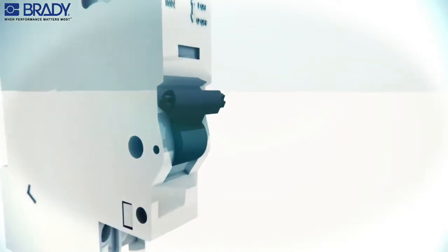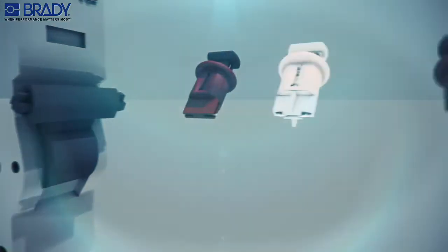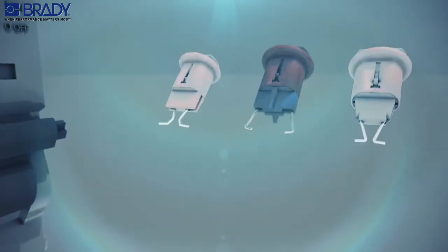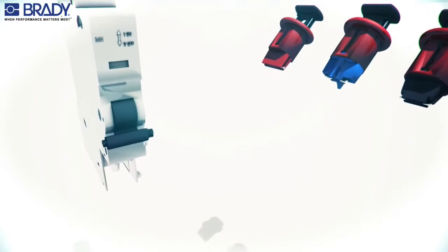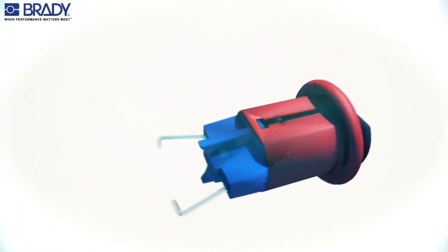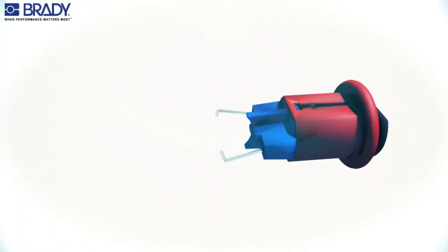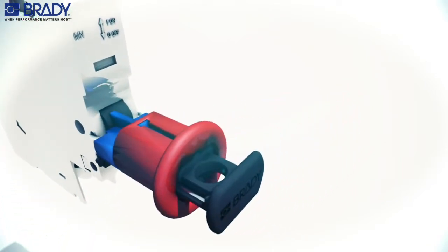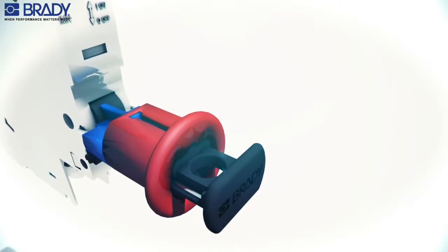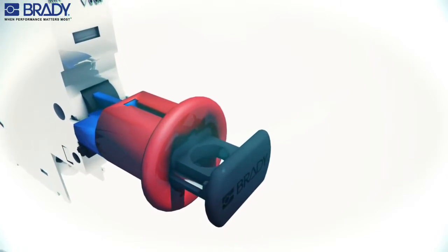Locate the small holes in the center of the circuit breaker casing. Select the appropriate pin-in or pin-out circuit breaker device. Place the circuit breaker in the off position. Press the lockout device push button to disengage the pins. Position the pins into the small holes of the casing by releasing the push button.